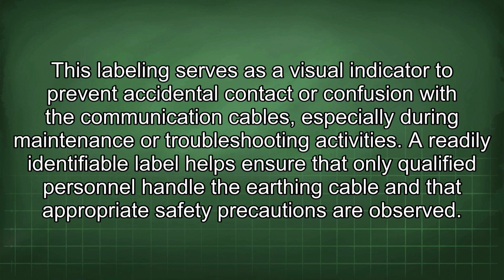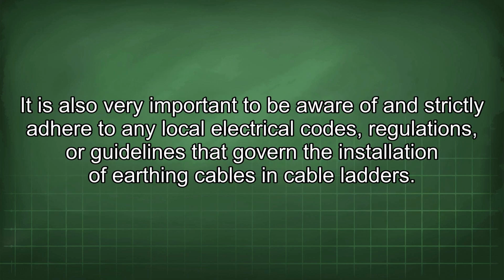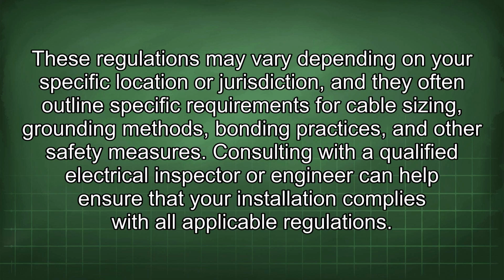A readily identifiable label helps ensure that only qualified personnel handle the earthing cable and that appropriate safety precautions are observed. It is also very important to be aware of and strictly adhere to any local electrical codes, regulations, or guidelines that govern the installation of earthing cables in cable ladders. These regulations may vary depending on your specific location or jurisdiction, and they often outline specific requirements for cable sizing, grounding methods, bonding practices, and other safety measures. Consulting with a qualified electrical inspector or engineer can help ensure that your installation complies with all applicable regulations.